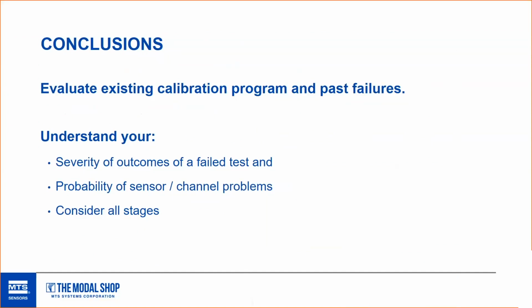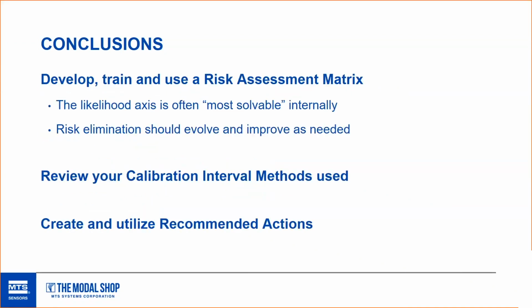Understand your severity of outcomes of a bad test, the probability of a sensor / channel problems, and consider all stages. Again, think about those poor three boxes that fell off the sensor cart after the cal lab. Does that happen where you are? And I think it's easy for all of us engineers involved to say, no, that never happens. But sensors often just don't up and turn bad over time. But make sure you use a risk assessment matrix internally. The likelihood axis is often most solvable. Your risk elimination should evolve and improve as needed. Review your cal interval methods used, and create and utilize a recommended actions table.